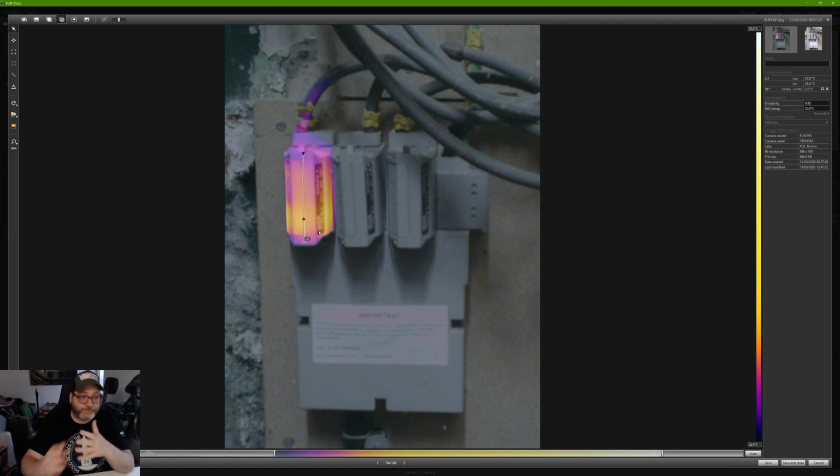And just so you know, this actual picture was done this way to the client, and it was recommended that this be looked at the next opportune moment, and it was put into the report that it needs to be looked at. And a couple months after my report was done, they went to this due to some other means, and they took the fuse holder down, and it had basically all burnt out.